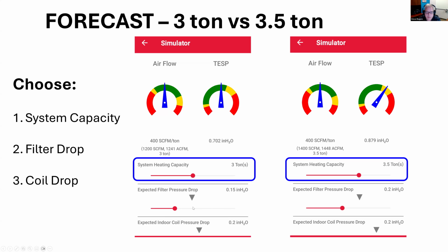And so I've looked up my information about the indoor coil pressure drop at 0.2. Let's say these are both available in an indoor coil that's about 0.2. And let's say with the filter pressure drop, I happen to know that the size of filter and the filter media that I'm going to install is going to be about 0.15 for 1200 CFM, but that same filter might be 0.2 if I need to move 1400 CFM. So knowing the filters that you use and how much pressure drop they create at various airflows is what you need to do this evaluation of the filters.